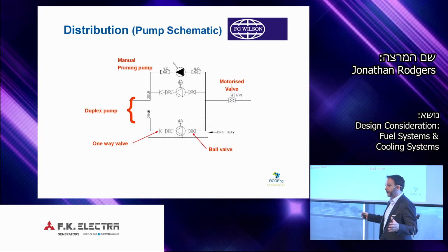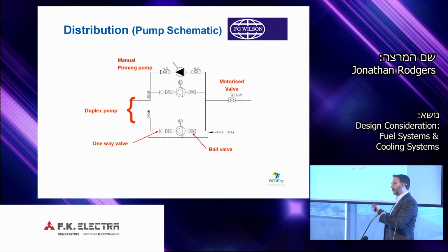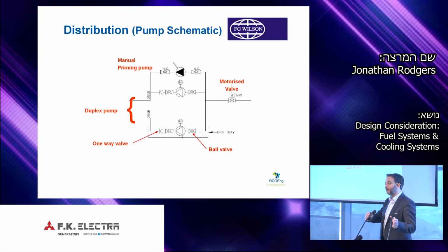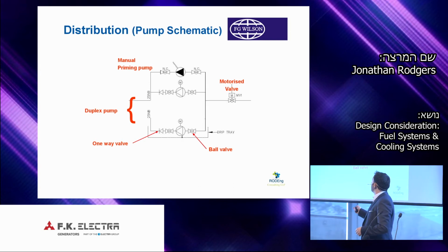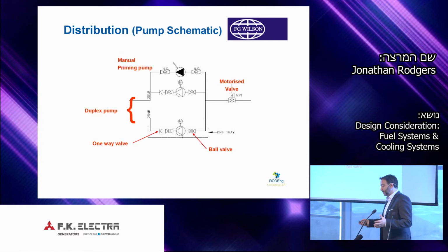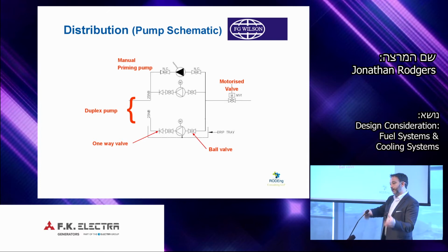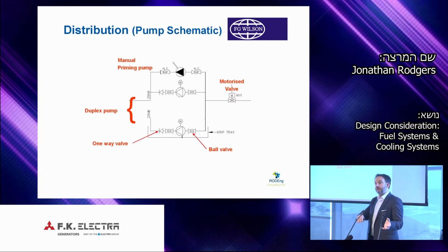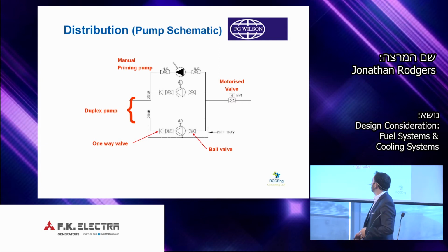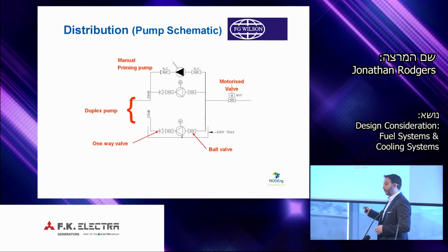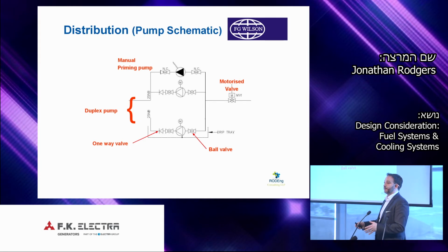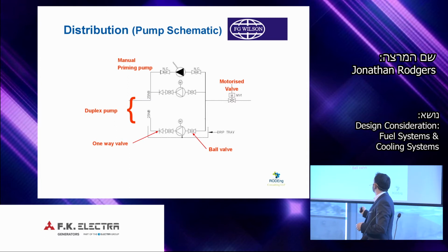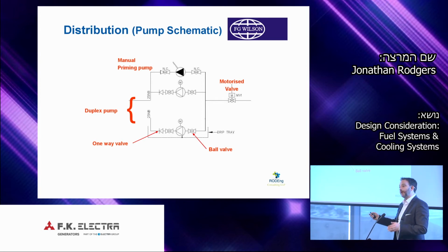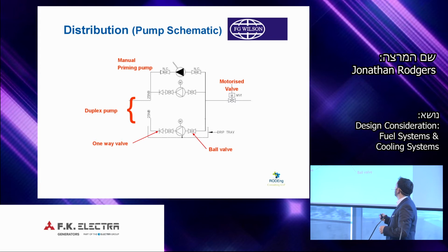So when we have our storage tank, we then need to transfer or move fuel from our storage tank to our day tank, our local tank. We have standard pump systems where it's a single pump between a large tank and a small day tank or local tank. But quite often, or more often, we have duplex pump systems, for resilience, so we have duty and standby. So one pump can operate, and if there is a fault, the other pump will automatically begin.